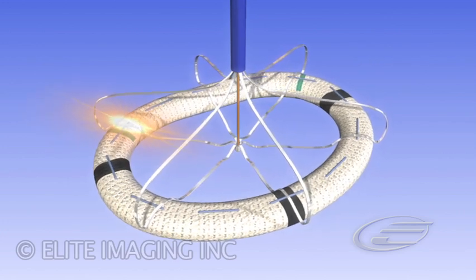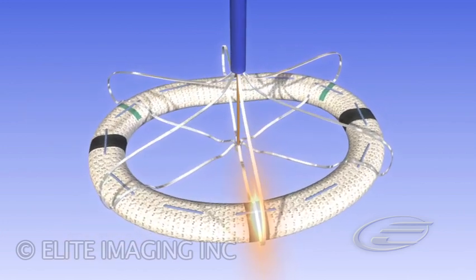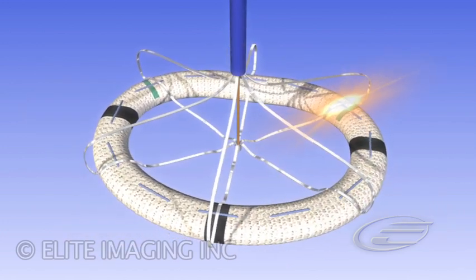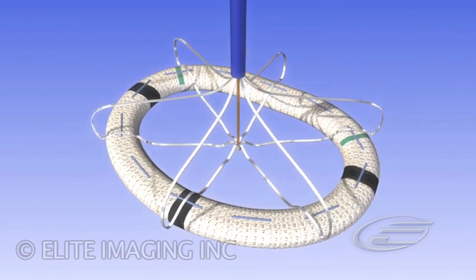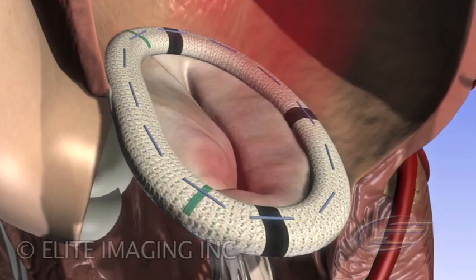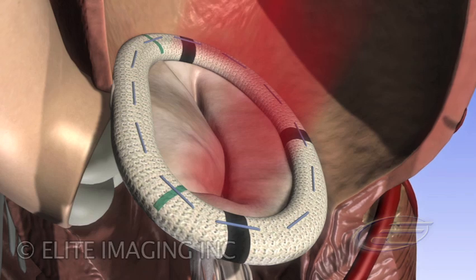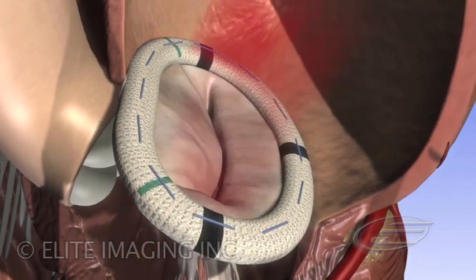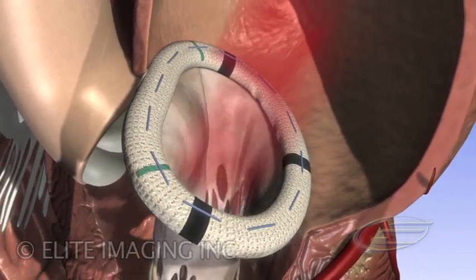Each electrode can be used to shape the area of the ring in its proximity. The zone closest to the energy electrode will move first with the greatest displacement. Once the reshaping is completed, as confirmed via echo and color flow Doppler mode, the mitral regurgitation is reduced.